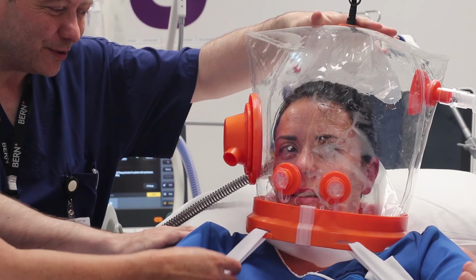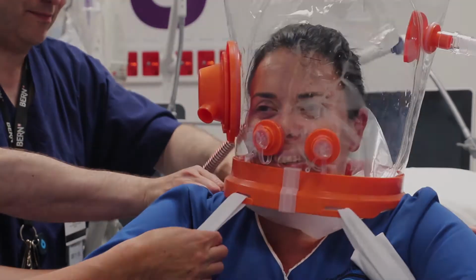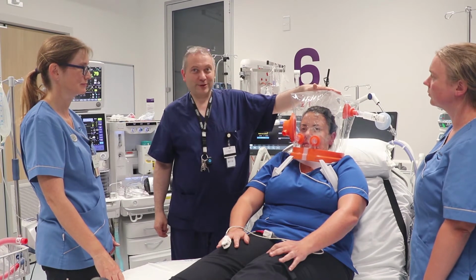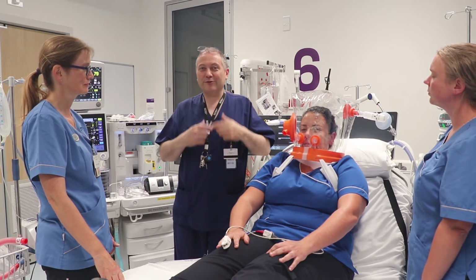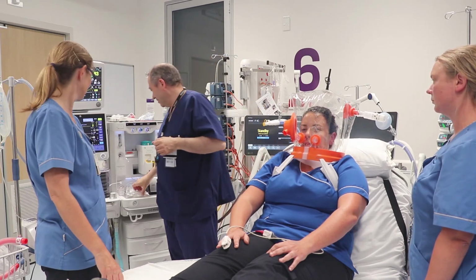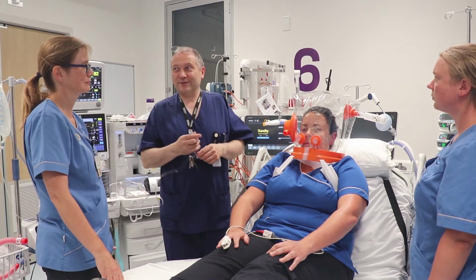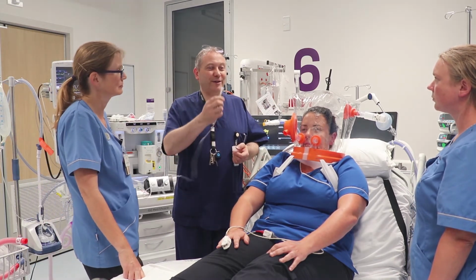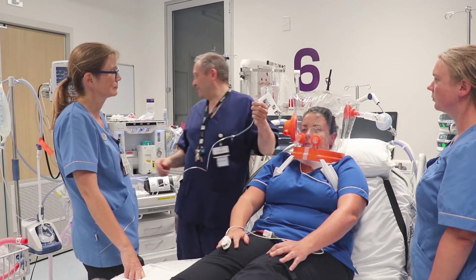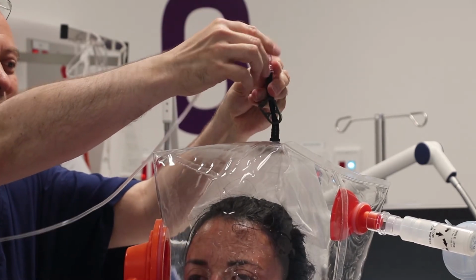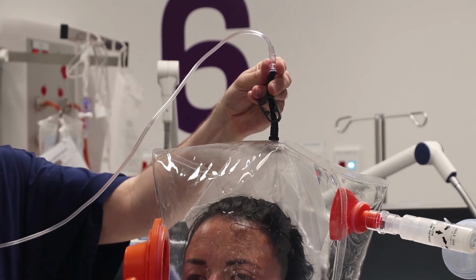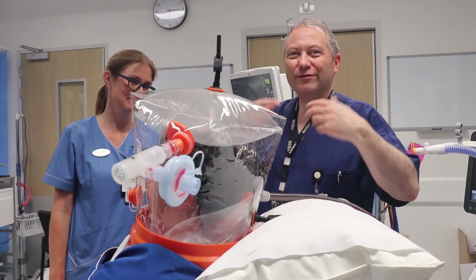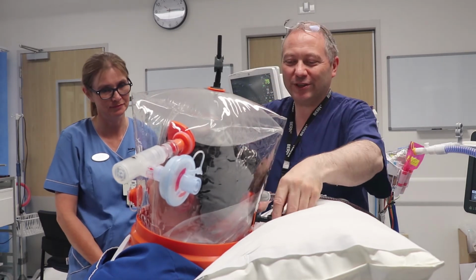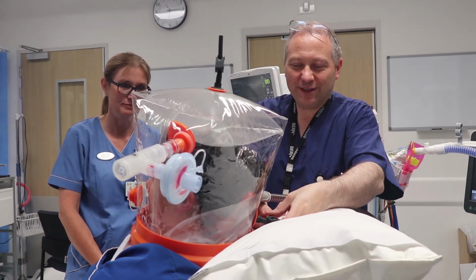Carla, may I just ask you to sit forward please, and we'll just tighten up the straps at the back. So next we're going to inflate the top cuff and the cuff that goes around the neck collar cuff. And this can be done with a standard luer tip syringe, or I'm going to use the oxygen, or you can use an air supply from the machine. And I'm just going to apply that there, and we can see the top cushion fill up. This will reduce some of the dead space in the helmet. So finally we're going to inflate the collar cuff that goes around the patient's neck. Again, this improves patient comfort. So next we're going to inflate the collar cuff.